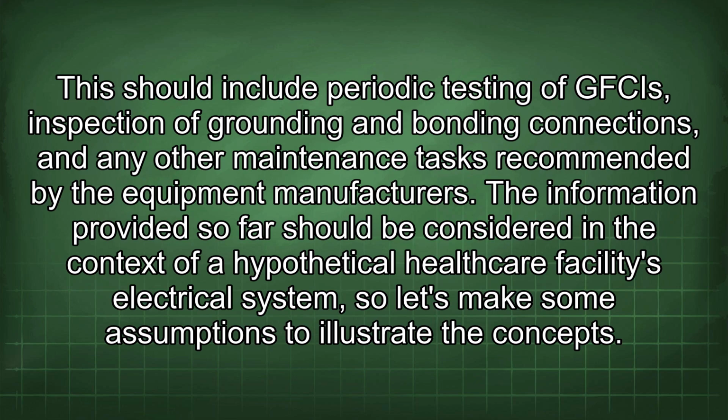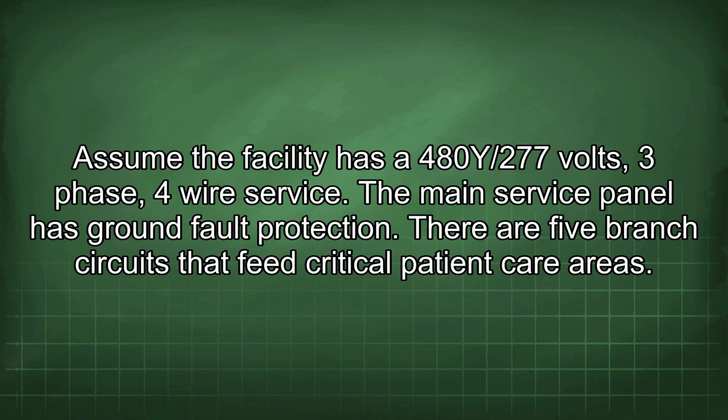the equipment manufacturers. The information provided so far should be considered in the context of a hypothetical healthcare facility's electrical system, so let's make some assumptions to illustrate the concepts. Assume the facility has a 480/277 volts, 3-phase, 4-wire service. The main service panel has ground fault protection.